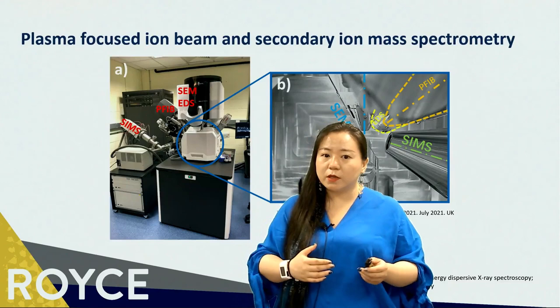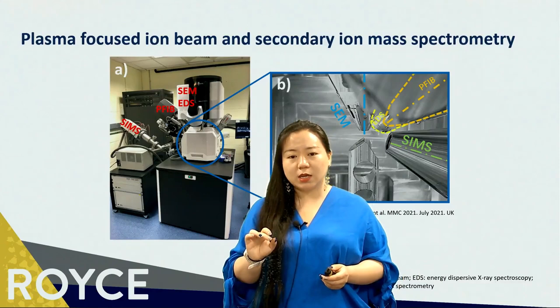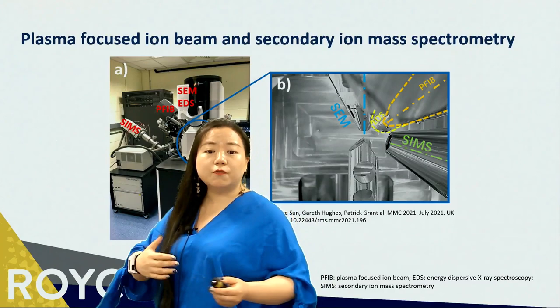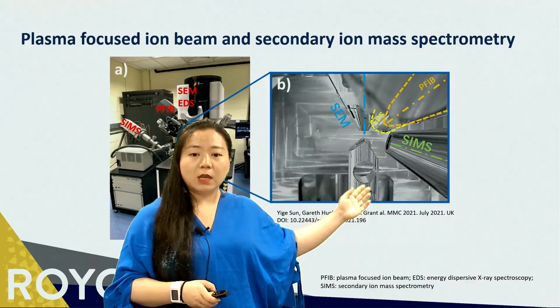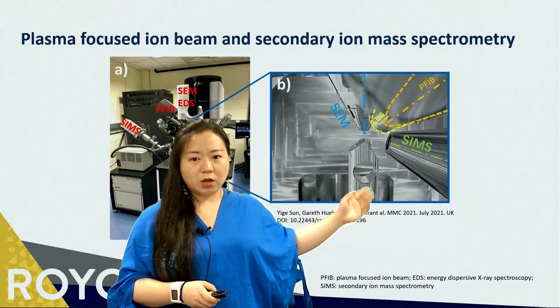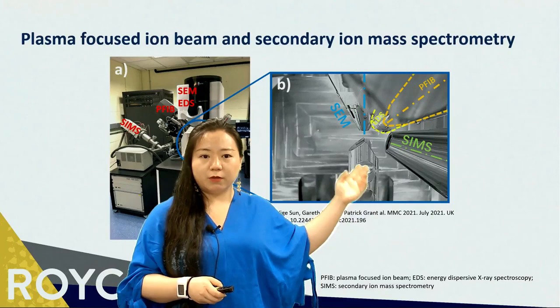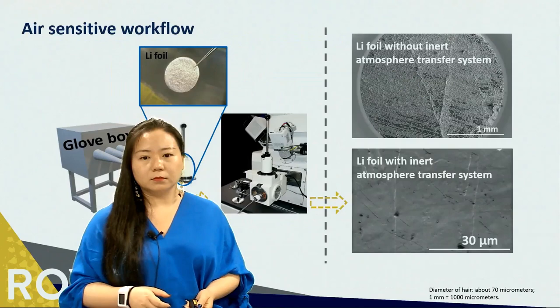However, the critical lithium distribution is not available from EDS due to the low X-ray energy and the low probability of emission. Therefore, here we use SIMS to detect the lithium ion distribution. To physically combine EDS and SIMS in this plasma FIB system, it is required to have a pre-tilted geometry and also the generation of new workflows, which combine imaging, cross-section milling, and data capture from these two detectors simultaneously.